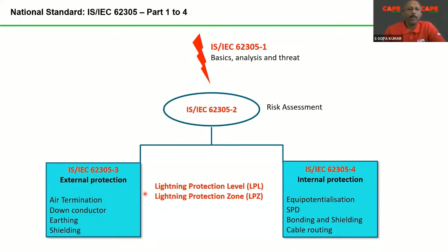When we talk about lightning protection, two theories are explained in the standard. One is the lightning protection level, and the second one is the lightning protection zone, the lightning protection zonal concept. In fact, the zonal concept is not only derived from the lightning protection standard. Zonal concept is derived from all the electrical safety, from the basic safety onwards. A kind of zoning has been carried out.